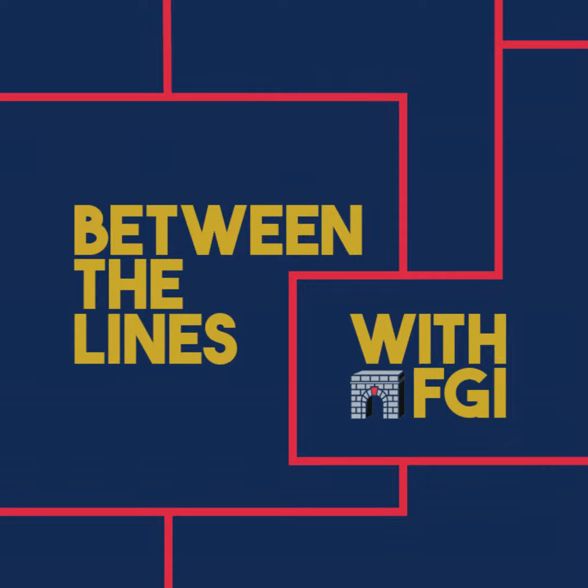I was one of the expert witnesses, and we got to do a forensic evaluation. We took apart the part of the quench pipe that has this burst disc. What is supposed to be there in a quench situation is nothing. You're supposed to have this big open hole that all of the pressure can escape through. However, when we opened it up, there were a couple of quarter-sized holes missing in this thin graphite membrane, but it was largely intact, which should be a physical impossibility. That was very strongly suggestive that there had been water accumulated.